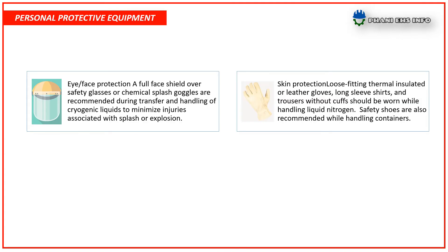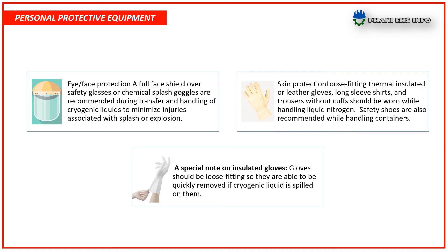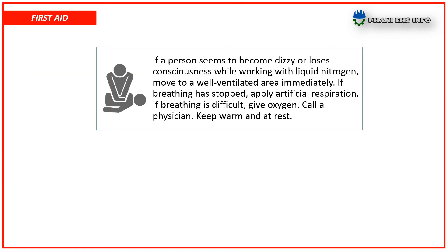Skin protection — loose-fitting thermal insulated or leather gloves, long-sleeve shirts, and trousers without cuffs should be worn while handling liquid nitrogen. Safety shoes are also recommended while handling containers. A special note on insulated gloves: gloves should be loose-fitting so they can be quickly removed if cryogenic liquid is spilled on them.